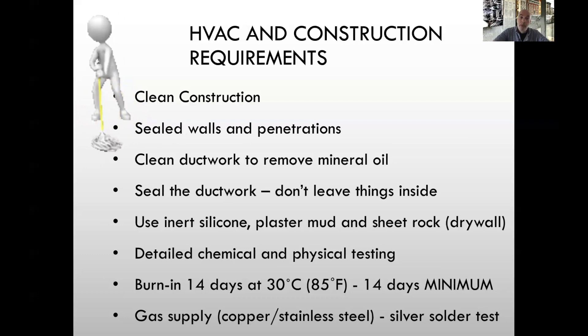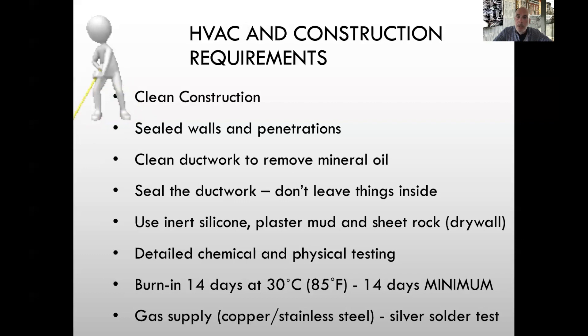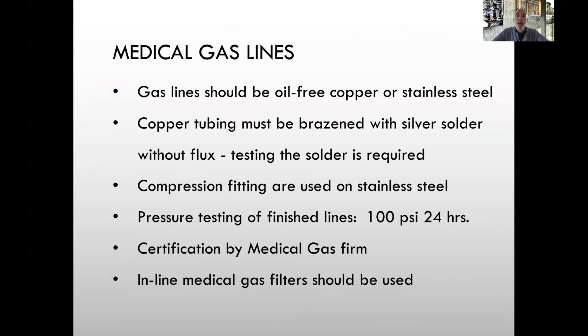For the gas supply, use either medical grade copper or medical grade stainless steel. If you use copper, you must have a silver solder test — it's the solder that's the problem, not the copper itself. Gas lines should be oil-free. Copper tubing must be brazed with silver solder without flux, and testing the solder is required. For stainless steel, use compression fittings. Pressure testing of finished lines must reach 100 PSI over 24 hours, and certification by a medical gas firm is required. Use inline medical gas filters on oxygen, CO2, and nitrogen lines.